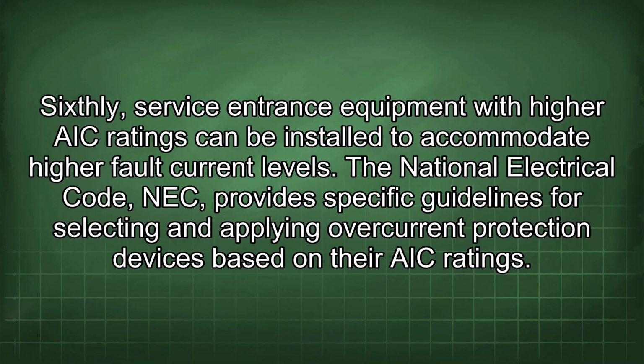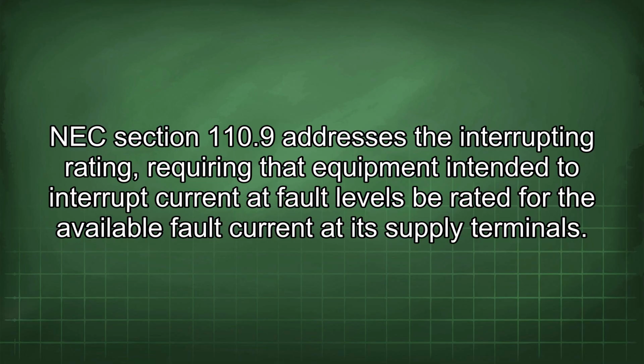The National Electrical Code, NEC, provides specific guidelines for selecting and applying overcurrent protection devices based on their AIC ratings. NEC Section 110.9 addresses the interrupting rating, requiring that the equipment intended to interrupt current at fault levels be rated for the available fault current at its supply terminals.